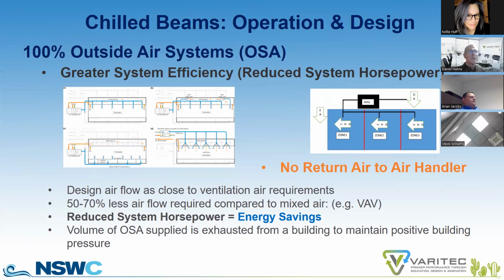And there's an added bonus with 100% outside air chill beam systems. There's no return air to an air handler. This is one of the reasons why ASHRAE was promoting on their epidemic task force to open up as much outside air as possible during the pandemic to continue flushing the building of any buildup of pathogens that occurs throughout the day. Because in order to maintain building pressure, you have to exhaust close to the amount of air that you supply so that you maintain building pressurization. So you have a continual flushing of the building with a DOAS system.